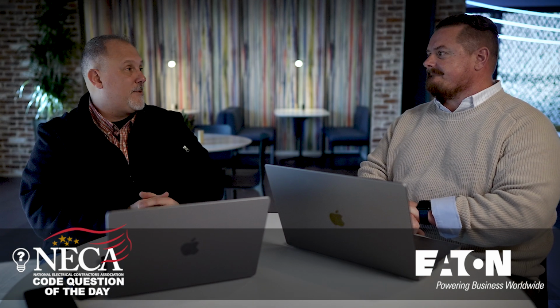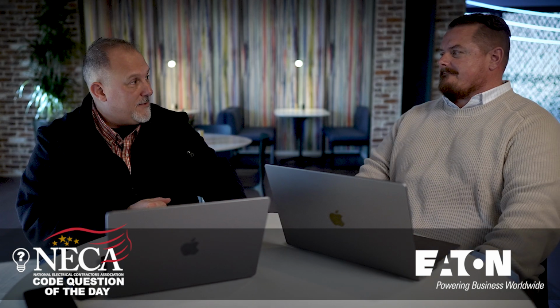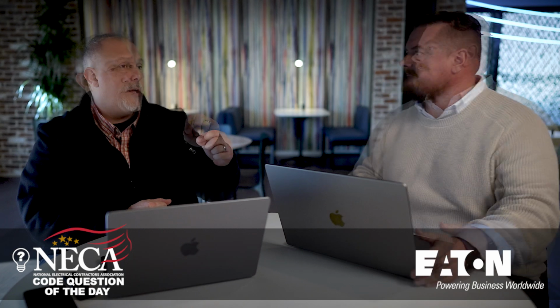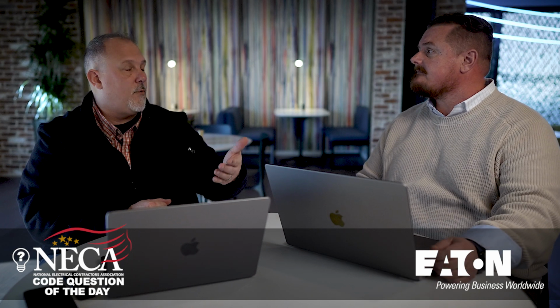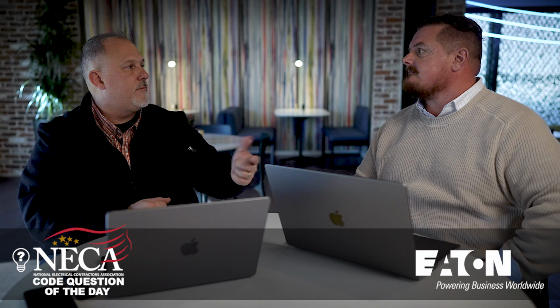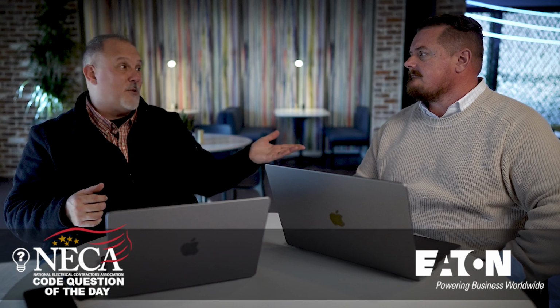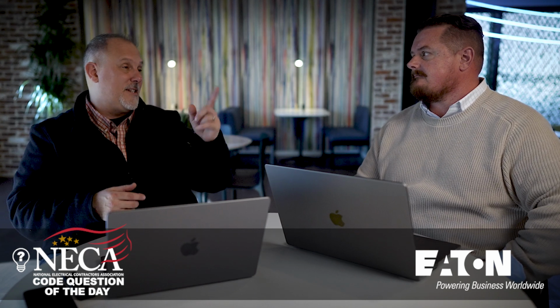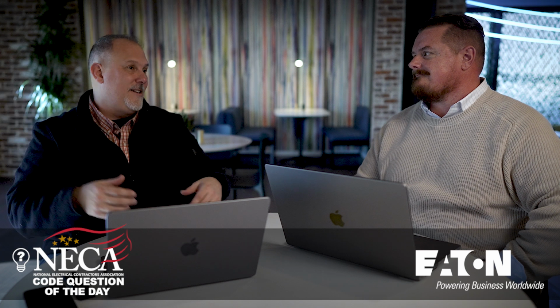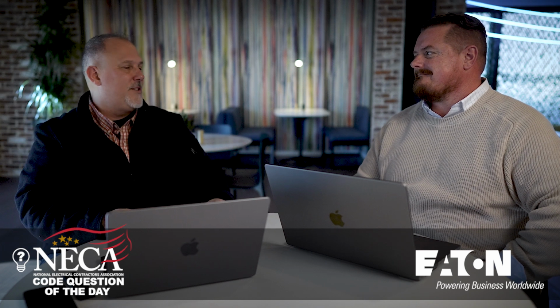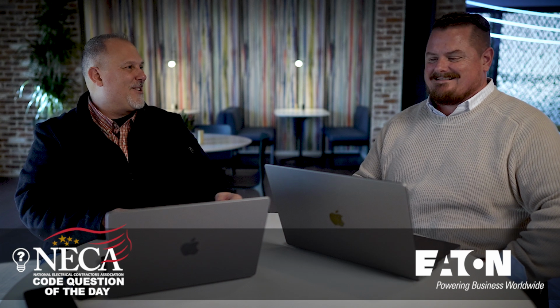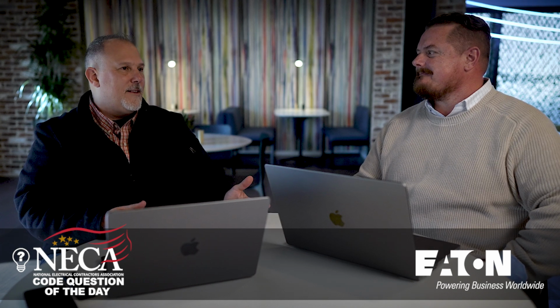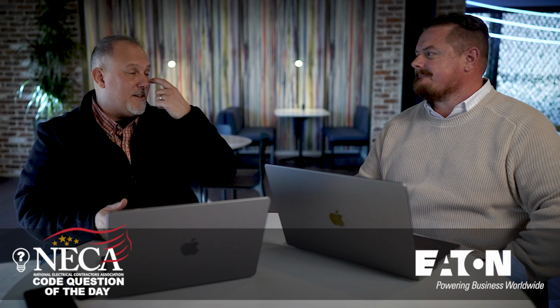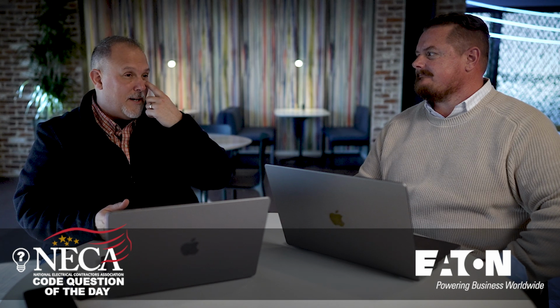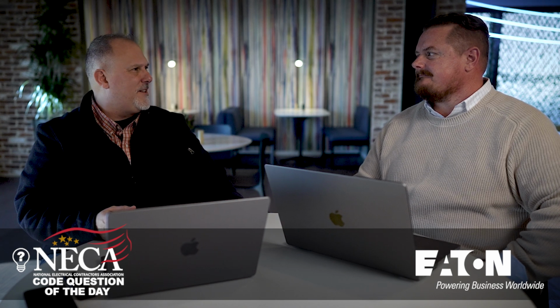Well, GFCI receptacle. I got burned one time on a GFCI. We had a project where we had a GFCI in a switchboard. Good inspector. He opens up the door. He sees the GFCI. He knows he's got 8,000 amps available fault current. So he says, that GFCI is over duty. So I got a call from the field, saying this inspector is rejecting the GFCI in the equipment. I'm like, I never heard of an SCCR on a GFCI.